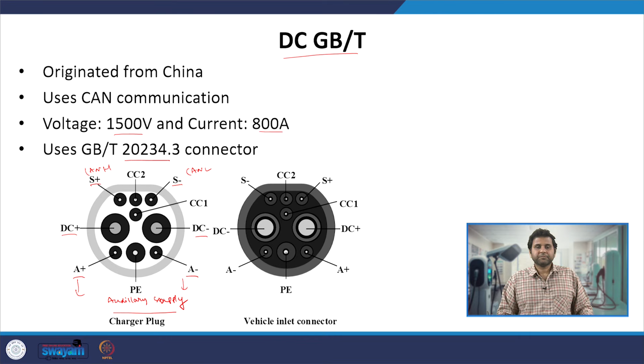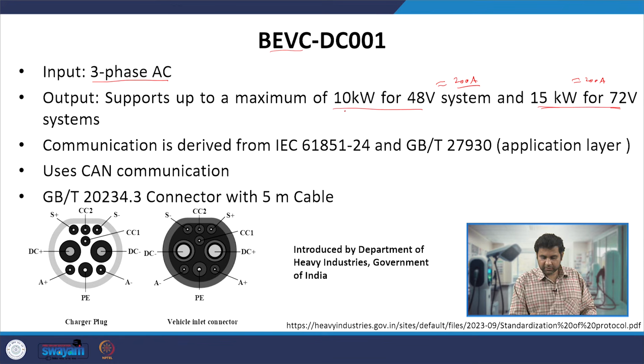Now in India, just like we have AC001, the Department of Heavy Industries also came up with BEVC DC001, which is the Bharat Electric Vehicle DC charging system, called DC001. In this, the EVSE has a 3-phase 415 volt AC input, and it supports a maximum of 10 kilowatt for a 48 volt system and 15 kilowatt for a 72 volt system. Here it supports a maximum of up to 200 ampere, which corresponds to nearly 15 kilowatt for a 72 volt battery system and 10 kilowatt for a 48 volt battery system.